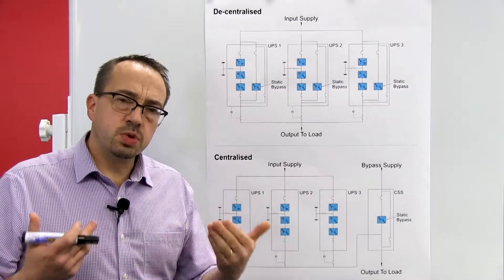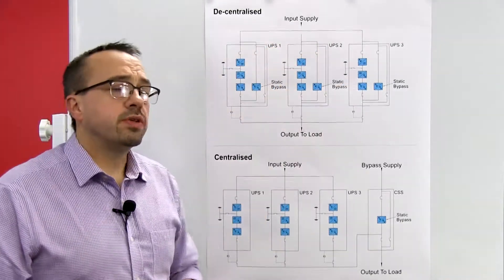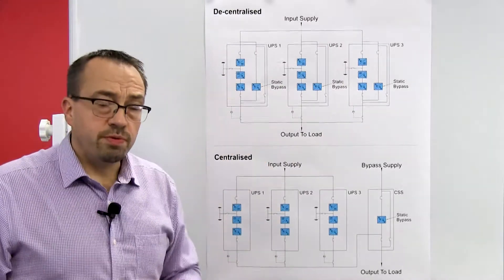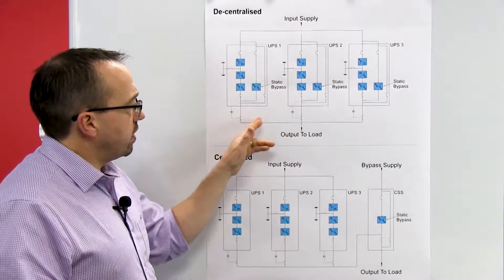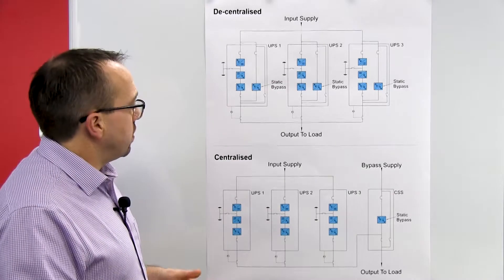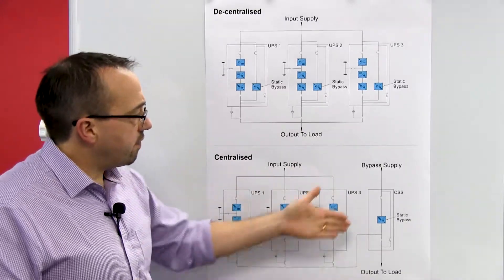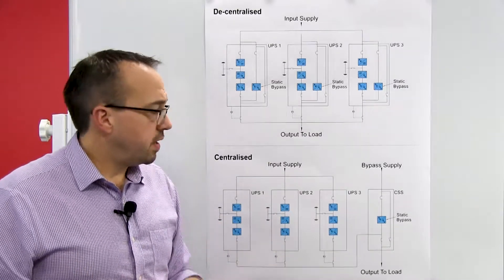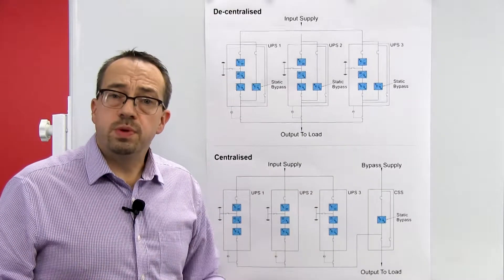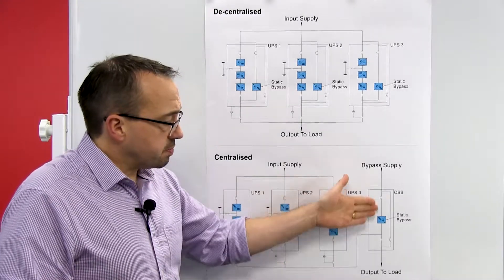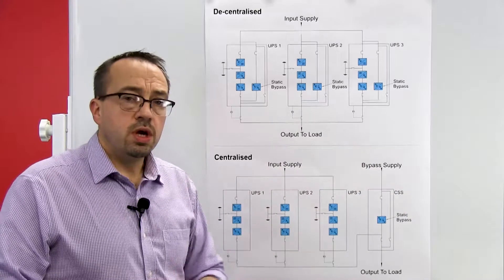You must also consider the switchgear requirements. In the decentralized system with a single supply input to each UPS, the breaker supplies both the rectifier and the bypass line, requiring only three input supply breakers and three outgoing load switches. However, with the centralized system you still have the same UPS input breakers and output switches, but the separate bypass cabinet requires an additional supply circuit breaker and output load switch — increasing switchgear cost. That bypass module must also be rated to the maximum power connected to the output, so the supply breakers to it could be significantly larger.